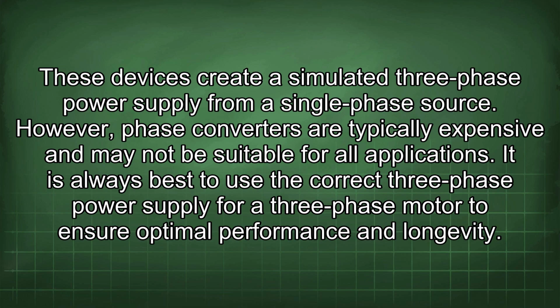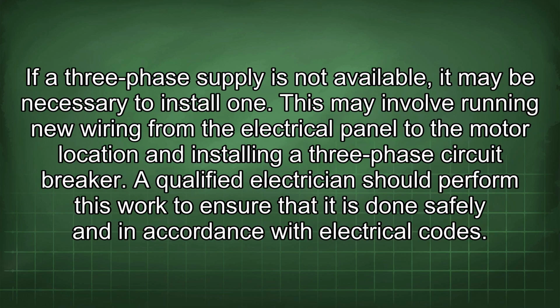It is always best to use the correct three-phase power supply for a three-phase motor to ensure optimal performance and longevity. If a three-phase supply is not available, it may be necessary to install one. This may involve running new wiring from the electrical panel to the motor location and installing a three-phase circuit breaker. A qualified electrician should perform this work to ensure that it is done safely and in accordance with electrical codes.